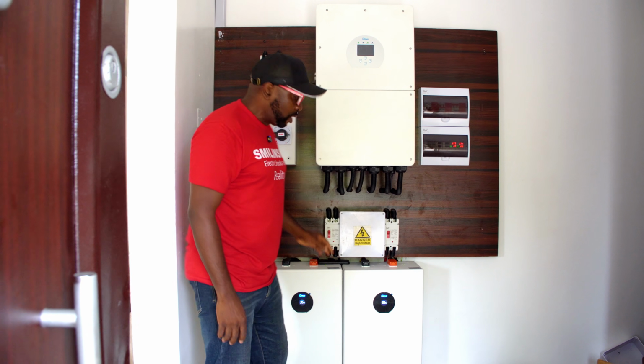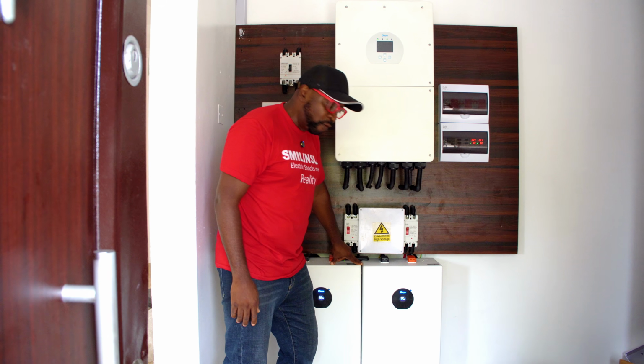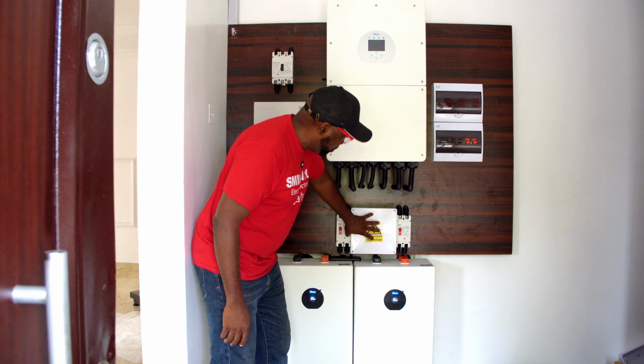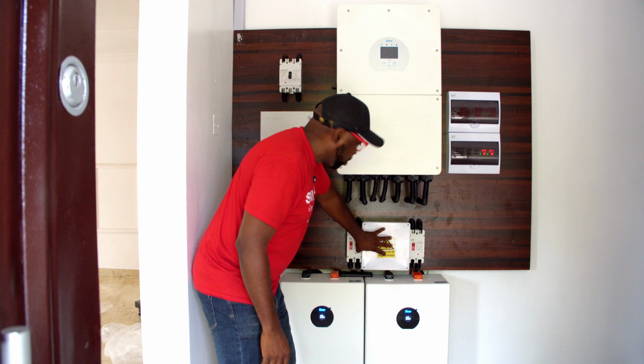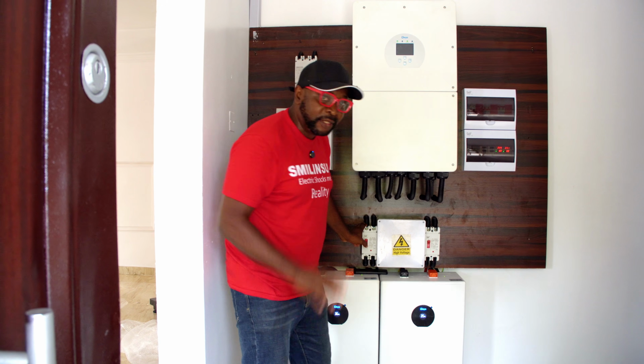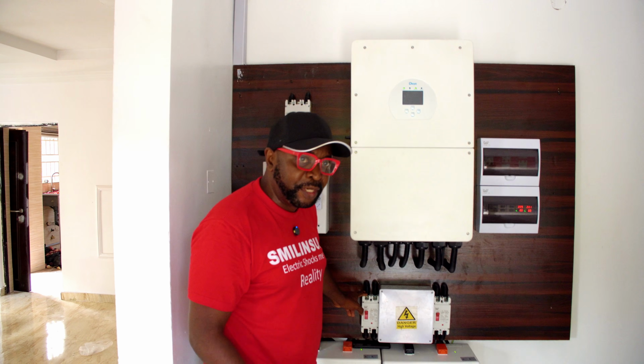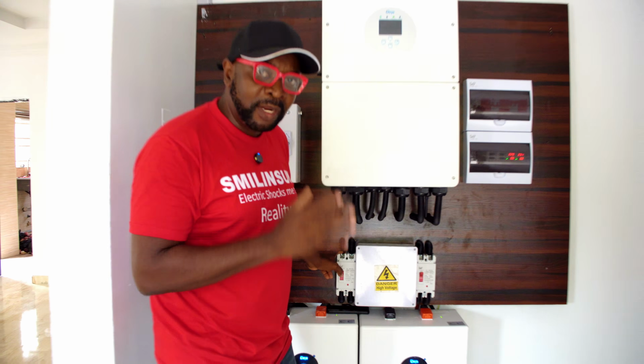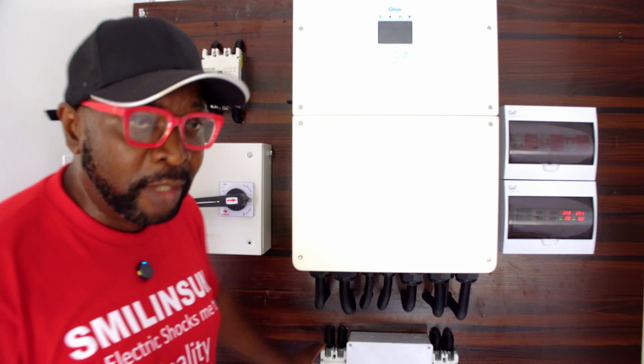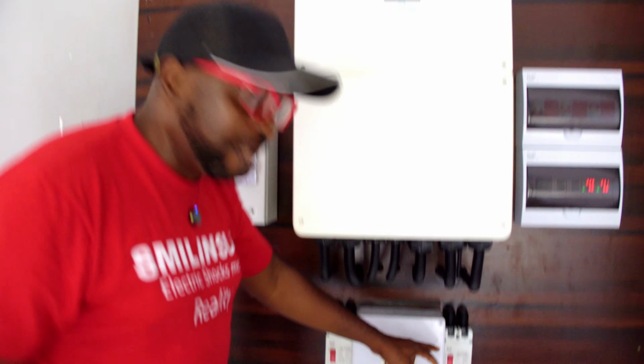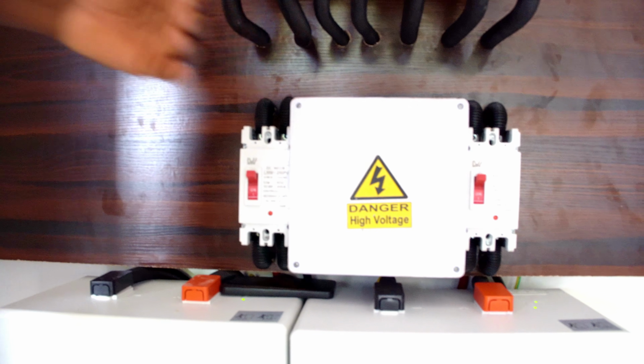We have 2 units of 16 kilowatt hour lithium battery, from Deye. Here is the bus bar, and flanking the bus bars on 2 sides are the MCCBs, each of them 250 amps - pretty good to respond appropriately if you have excessive current or want to do maintenance. These guys will be there to ensure the damage does not go beyond where it's supposed to.